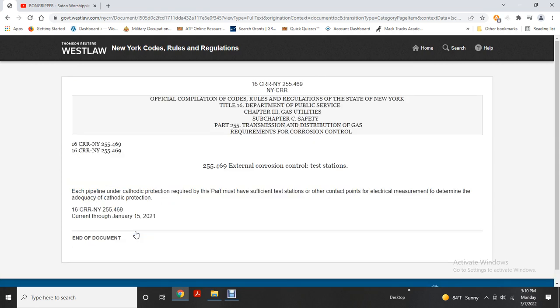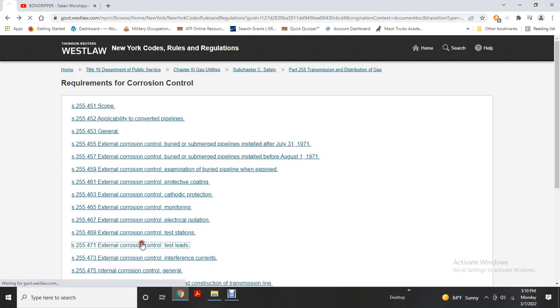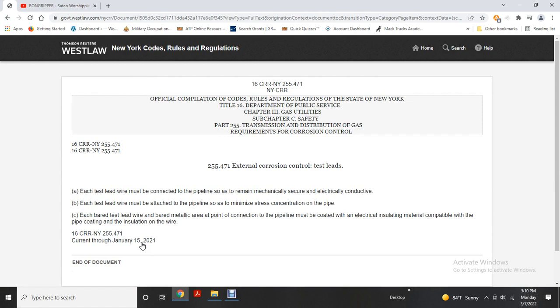External corrosion test stations: each pipeline under cathodic protection must have sufficient test stations and other contact points to allow electrical measurements that determine the adequacy of cathodic protection. Each test lead wire must be connected to the pipeline so it will remain mechanically secure and electrically conductive. Each test lead wire must be attached to minimize stress concentration on the pipe. Each buried test wire and the area at the point of contact with the pipeline must be coated with electrical insulating material compatible with both the pipe coating and the wire insulation.